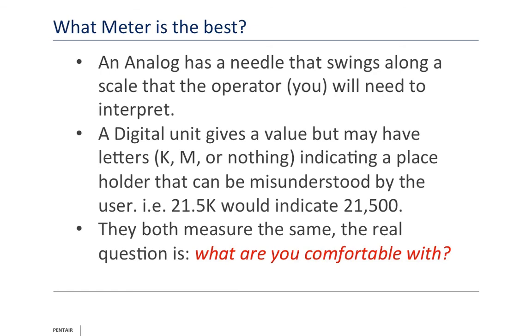So say, for example, I have a meter that I can check ohms with, and I can set the scale, and I set it to 200 ohms. If my motor is so badly damaged it's reading 207 ohms, it wouldn't show 207 because the upper limit is 200. It would say OL or L or 1 period all the way to the left, telling you it's not overloaded, it's out of the limit that you're trying to read. So in that case, I would disconnect my wires, turn my meter from 200 to, say, 2,000 ohms, reconnect the wires, get my reading, and now I would see that 207 or 492, whatever it was over the 200, it could not read. So you have to understand how these meters work.